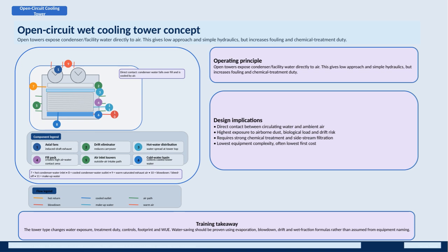From a design standpoint, there are several important components to note. Axial fans induce airflow, while drift eliminators minimize water loss by reducing carryover. Water is distributed evenly over the fill pack to maximize cooling efficiency, and air inlets draw outside air into the tower. Cooled water collects in the cold water basin before returning to the condenser. Key flows include the hot water entering the tower, cooled water exiting, the air path to the system, blowdown or bleed off to control impurities, and makeup water to compensate for losses.